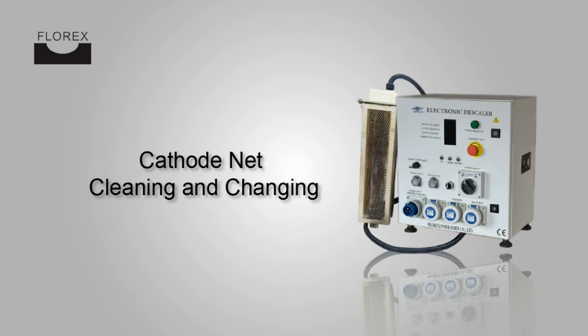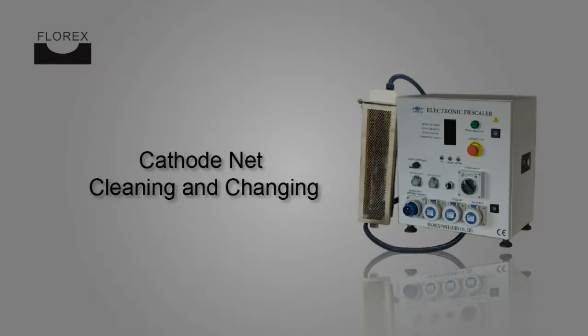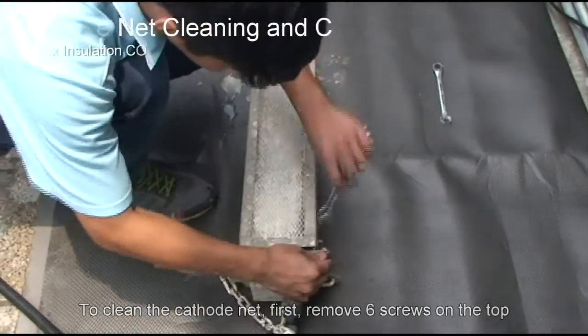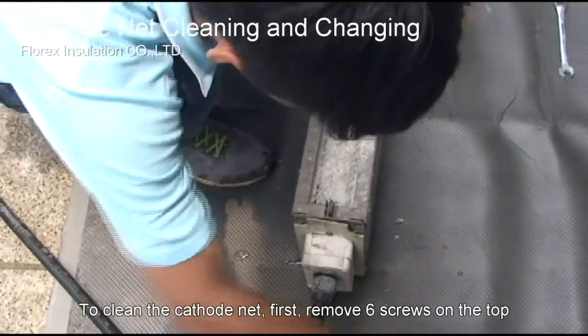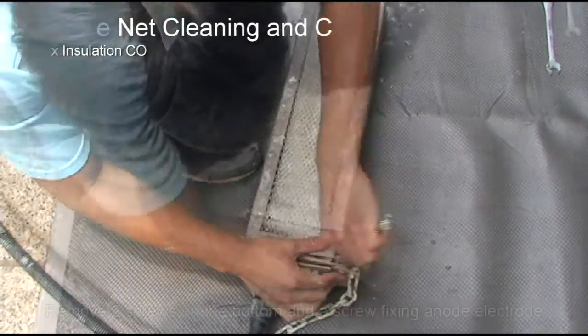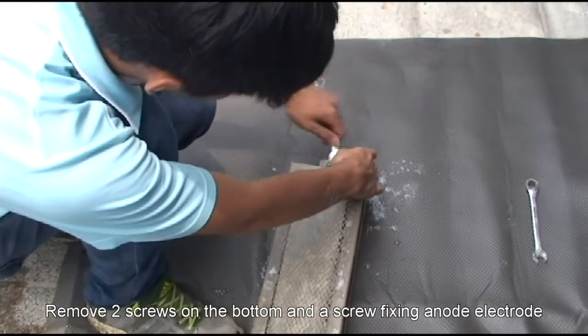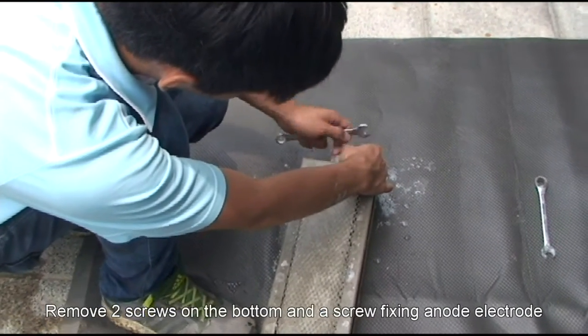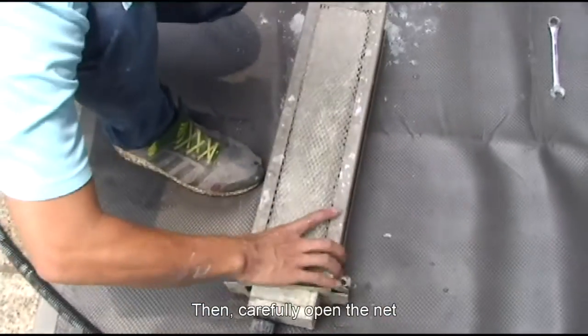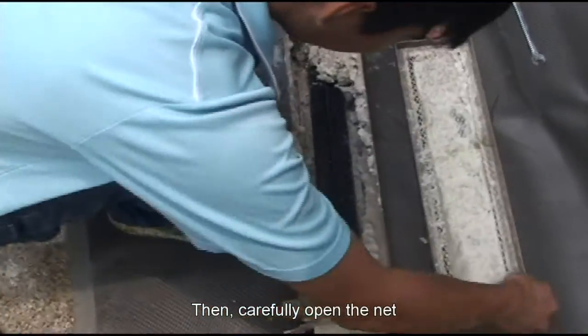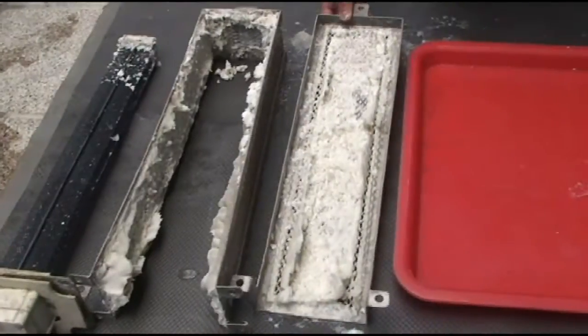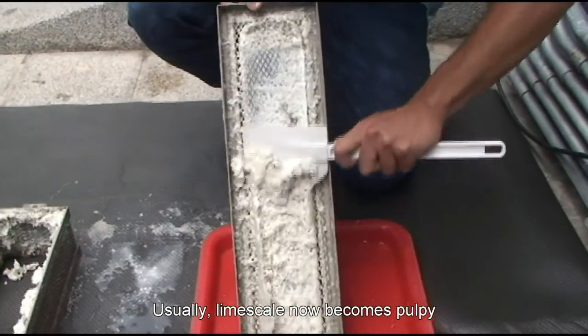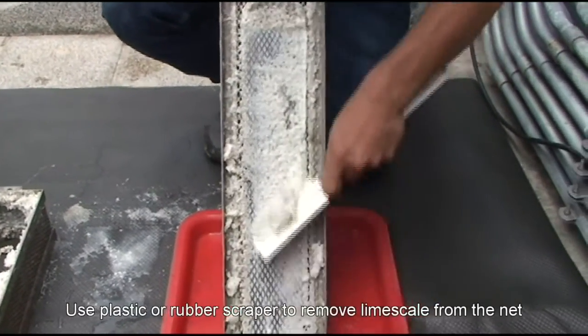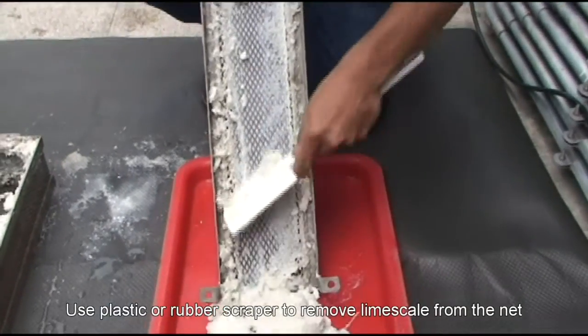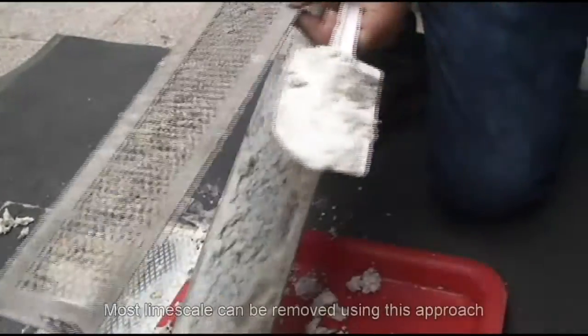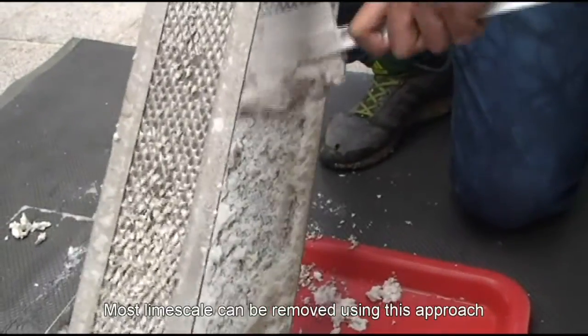Cathode net cleaning and changing. To clean the cathode net, first, remove 6 screws on the top. Remove 2 screws on the bottom and a screw fixing anode electrode. Then, carefully open the net. Usually, limescale now becomes pulpy. Use plastic or rubber scraper to remove limescale from the net. Most limescale can be removed using this approach.